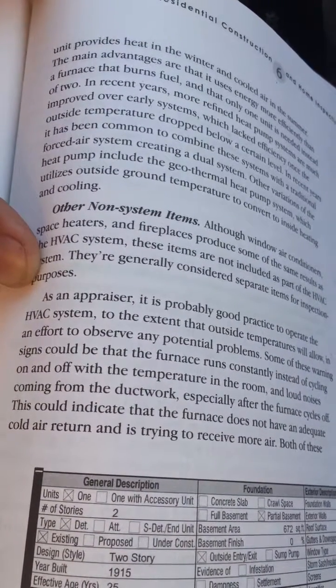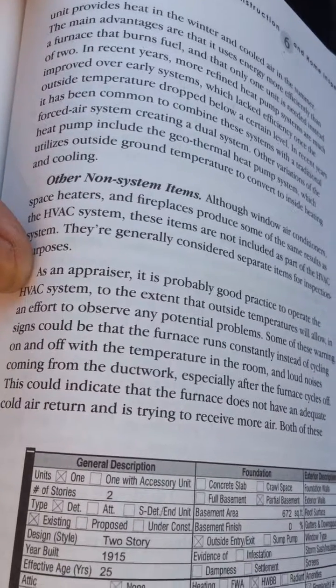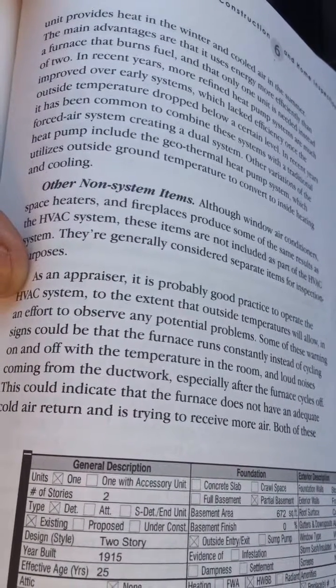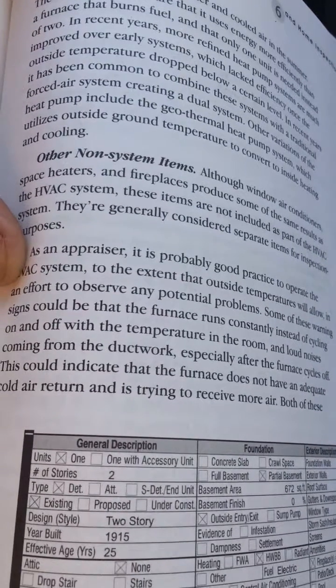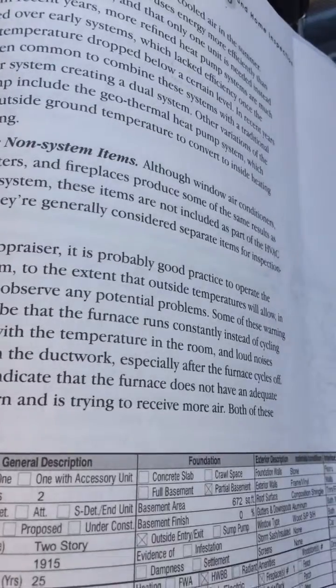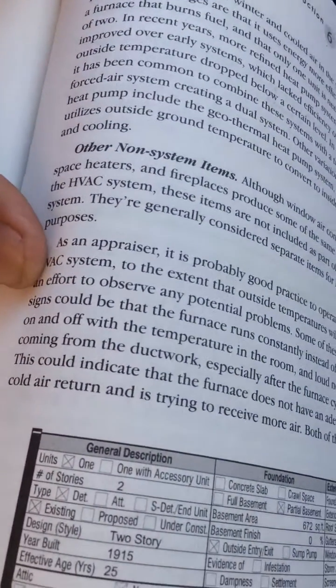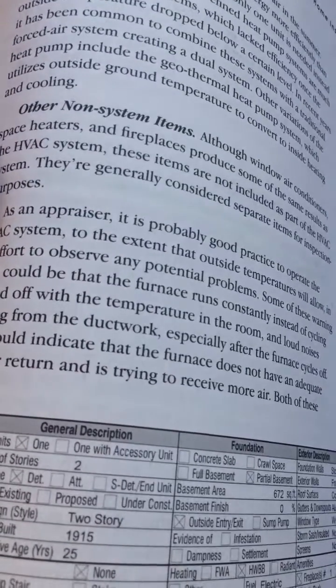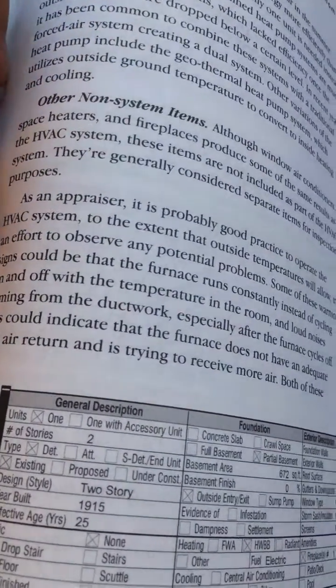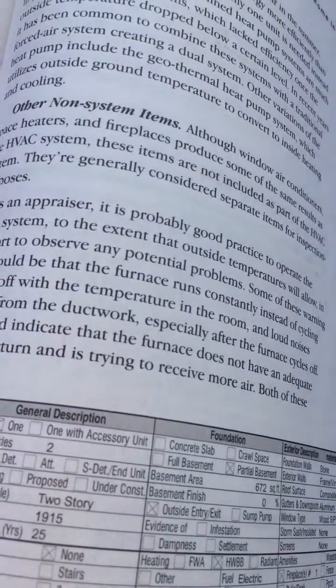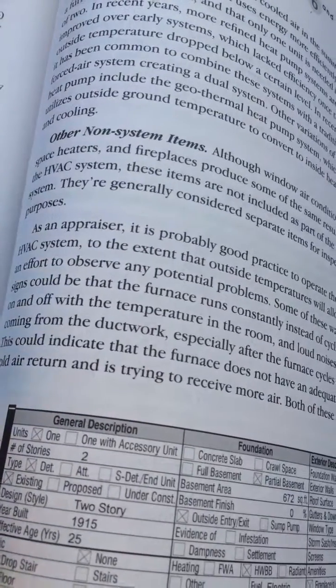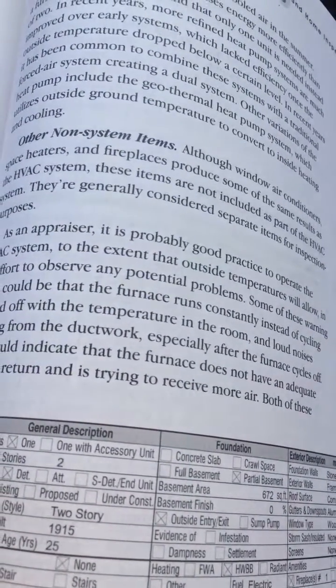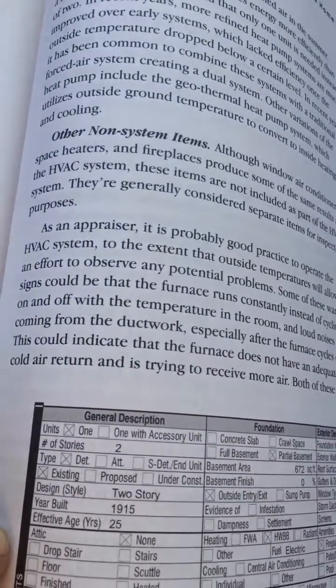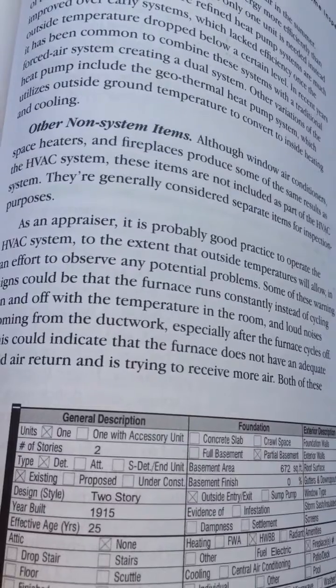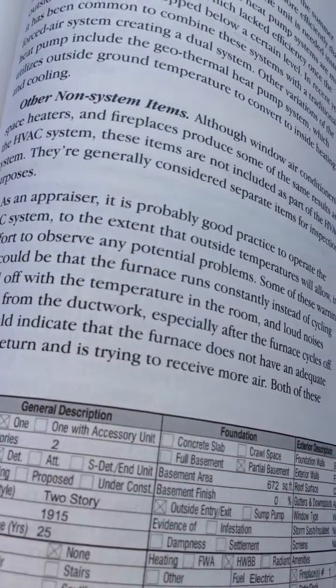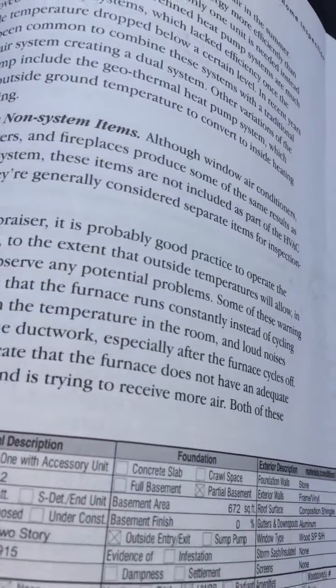As an appraiser, it is probably good practice to operate the HVAC system to the extent that outside temperatures will allow, in an effort to observe any potential problems. Some of these warning signs could be that the furnace runs constantly instead of cycling on and off with the temperature in the room. The loud noises coming from the ductwork, especially after the furnace cycles off. This could indicate that the furnace does not have an adequate cold air return and is trying to receive more air.